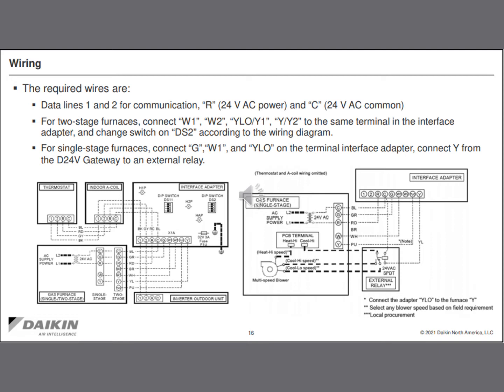And this slide here covers our 24 volt wiring to our legacy gas furnace, or our non-communicating gas furnace. This is going to look a little bit different in each application depending on the brand and style of furnace that you're wiring up to, but it's still going to follow the same format. At the gateway, we're going to have RC, data 1 and data 2 going to our EEV coil and to our outdoor unit. But we're also going to have 24 volt connections going to our existing gas furnace. If we have a two-stage furnace, we're going to have W1, W2, Y low and Y1, or Y and Y2, depending on how your unit is labeled. Single stage gas furnaces are just going to use G, W1, Y, and are going to be pretty straightforward.